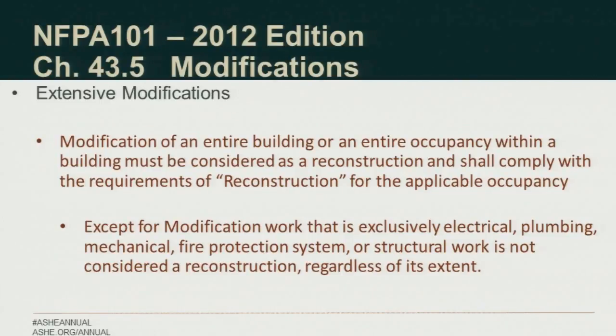modifications of an entire building or an entire occupancy within a building must be considered as reconstruction, which we'll touch on next, and shall comply with the requirements of reconstruction for the applicable occupancy chapter. The exception is that modification work that is exclusively electrical, plumbing, mechanical, fire protection, or structural work is not considered reconstruction regardless of the extent.